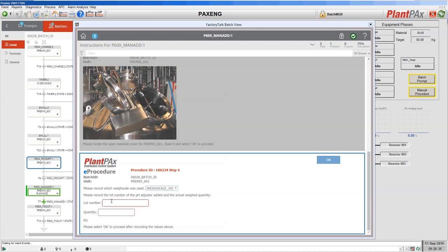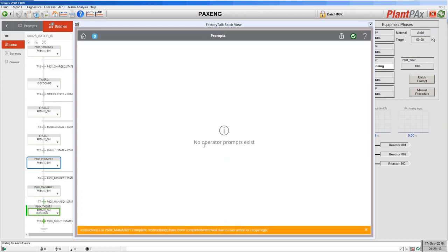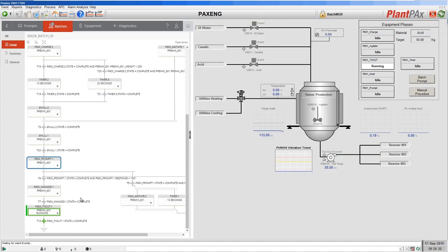We go and choose the weighscale that we've used. This asks us to record the lot number of the material that we've added, and that could be filled in by barcode scan of the bag that was used — I shall manually type it in. We're being asked to confirm the quantity that was added. This entry can be intelligent: you can set up limits, so if the amount added was more than 2% from the amount asked to add, you would again require a signature before proceeding. Let's put in a value within 2% and confirm that step. Our manual procedure has now completed. There are no more prompts to follow, and if we go back to our FactoryTalk View display, we've now moved on to the next step in our recipe — to transfer the material out into the reactor.